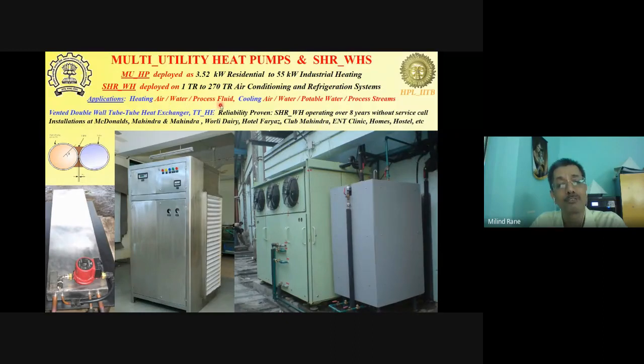It can heat process fluids directly because of this reliable heat exchanger. We could heat up the process fluid, that is the cleaning solution, directly with our condenser heat. Normally, heat pumps will heat up water, a clean stream of water, and then that clean stream of water would be used to heat the process stream, thereby adding one more heat exchanger, one more recirculation loop, and so forth.